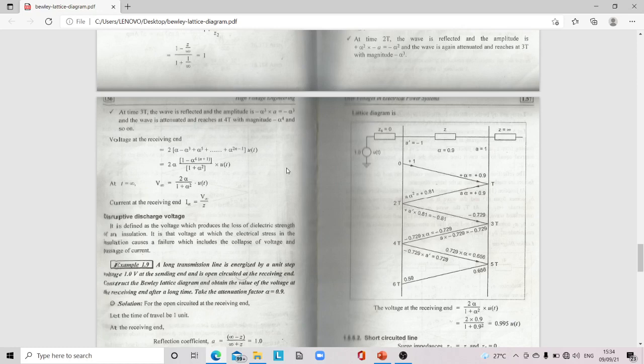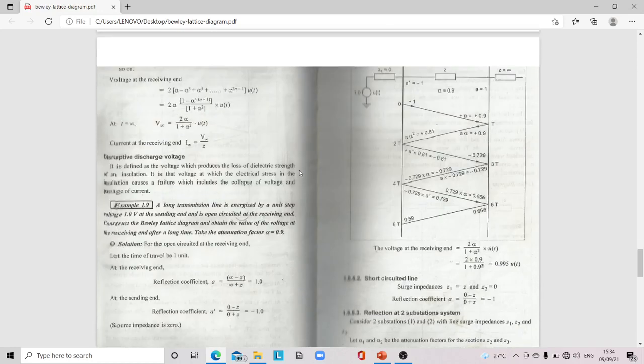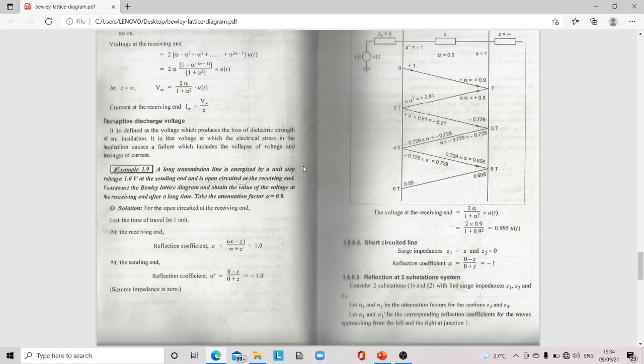Disruptive discharge voltage is defined as the voltage which produces loss of dielectric strength of an insulation — the voltage at which electrical stress causes failure including collapse of voltage and passage of current. Numerical example: a long transmission line is energized by a unit step voltage of 1.0 V at the sending end and is open-circuited at the receiving end. Construct the Bewley lattice diagram and obtain voltage at the receiving end after a long time. Take attenuation factor α = 0.9. At receiving end: reflection coefficient = 1.0. At sending end: reflection coefficient = −1.0. Voltage at receiving end = 2α/(1 + α²)·u(T) = 0.995·u(T).